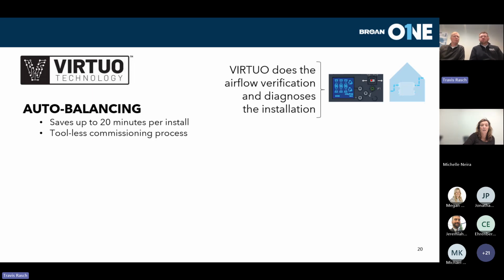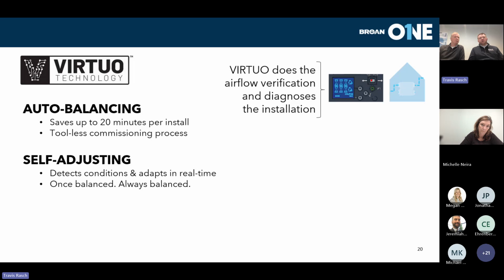For those familiar with ERVs or balanced ventilation technology, balancing is critical to overall performance, making sure the pressure inside the dwelling is neutral or balanced. This Virtuo technology does that balancing step for you automatically at startup, instead of using manometers or manually adjusting balancing dampers. Any manual intervention needed for balancing is done at the beginning, and the product stays balanced throughout its operational life.